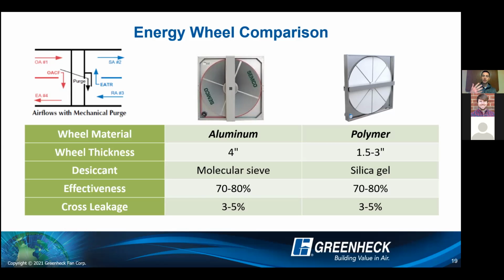The aluminum wheel does come standard with a purge section, but we don't really have the calculations in place, and the AHRI certifications that they report are without that purge section. So that's why technically we're still promoting that 3 to 5% cross contamination. But just so you know, that aluminum wheel does come with the purge section. And if you need the polymer wheel with the purge, we do offer that via a special design, something that you can work with Holden.